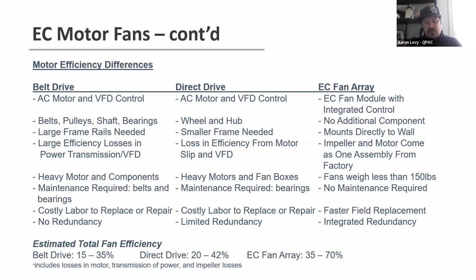Direct drive systems for cubes and things like that, there is some limited redundancy because they'll use bigger motors, anywhere from 2 to 4, and you could lose 25% of your airflow. For the QPAC style system, we integrate a lot of that redundancy, so it's almost N+1 for a lot of cases, where if a fan goes down, the rest of them will spool up automatically to compensate for that fan, and the customer never feels even an interruption in their system.